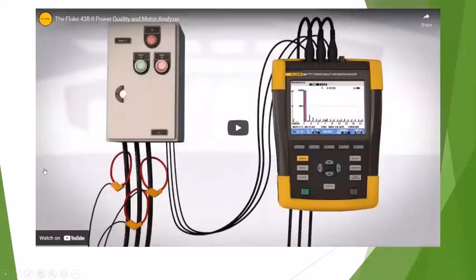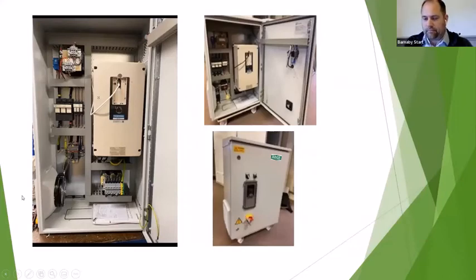Any other points you want to bring up on that, Barney, on the drives? Yeah, sometimes if we go very large on the AC systems or DC, we go 12 pulse, so maybe half megawatt. In the UK, it differs around the world, but probably around half megawatt and above, we would try and put a 12 pulse system in. So basically we'd fit a transformer in, which would split our three phases into six phases. Then you take three phases into one drive and three phases into the other. That would help the harmonics and the voltage disturbance with the supply, because like you say, you get third and fifth harmonics, which become increasingly a problem as you go up in size.